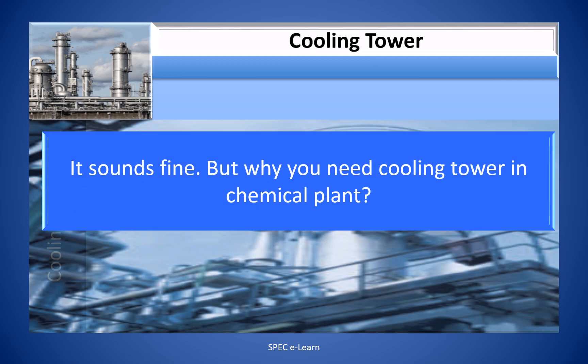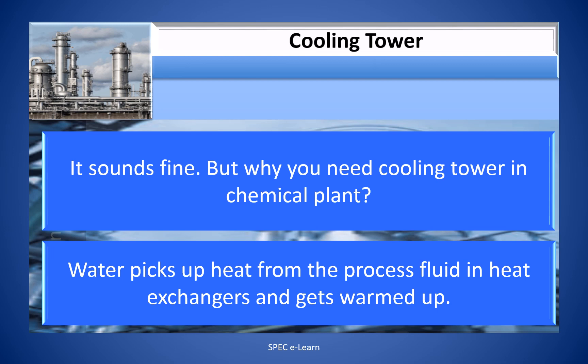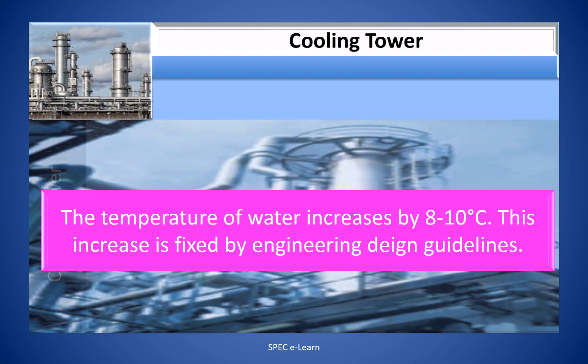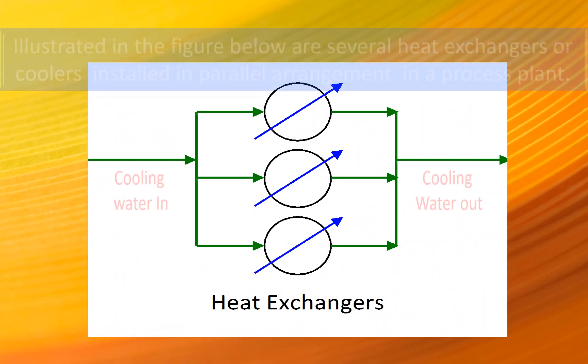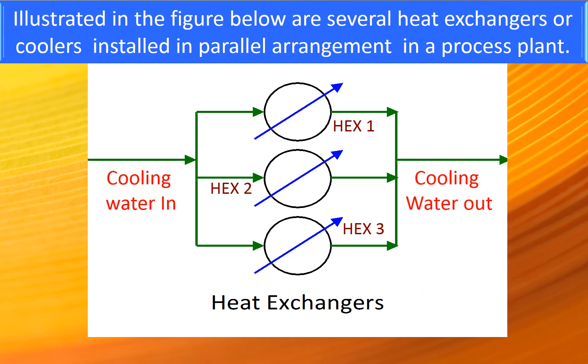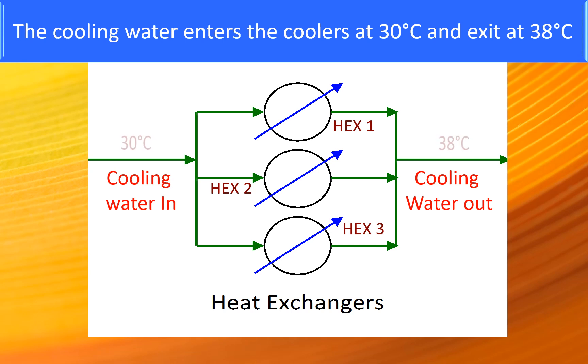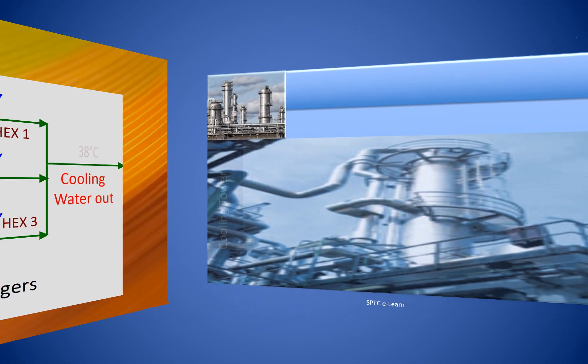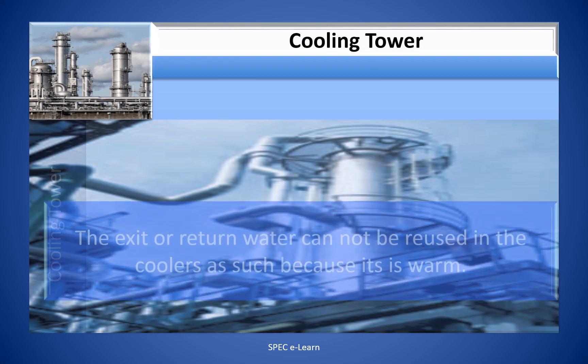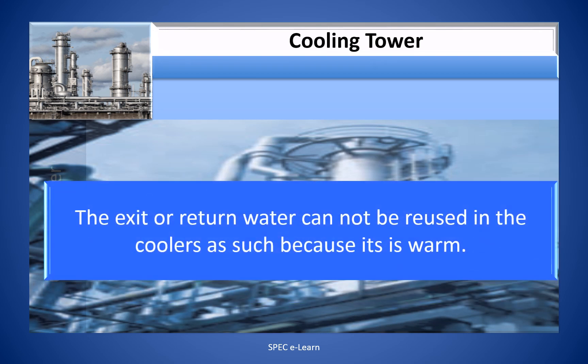But why do you need a cooling tower in a chemical plant? Water picks up heat from the process fluid in heat exchangers and gets warmed up. The temperature of the water increases by 8 to 10 degrees centigrade, fixed by engineering design guidelines. Several heat exchangers installed in parallel — cooling water enters at 30°C and exits at 38°C.